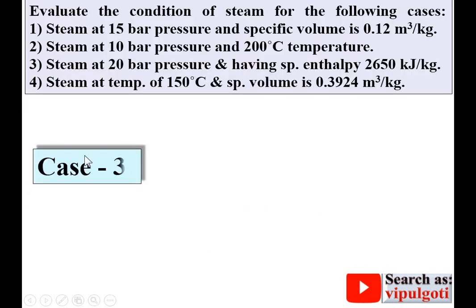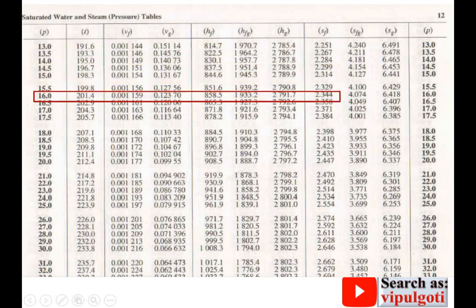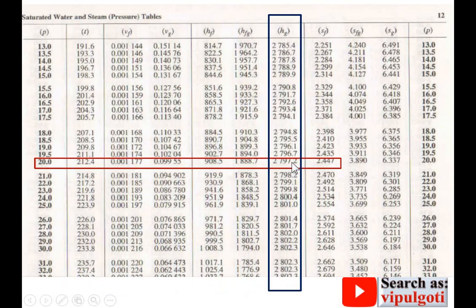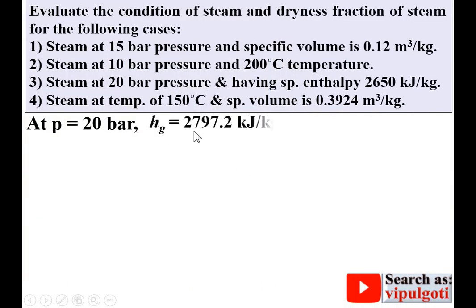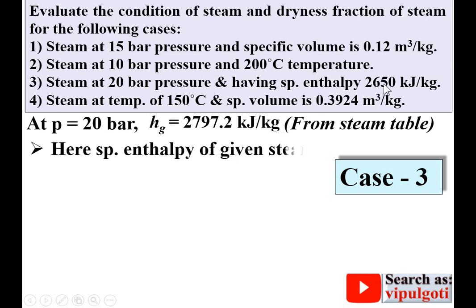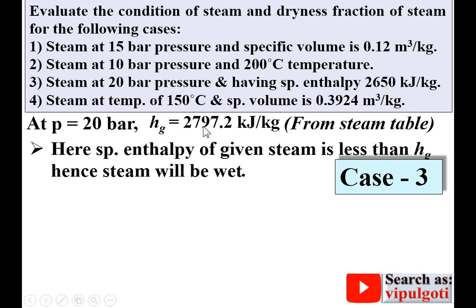Case three: steam at 20 bar pressure with specific enthalpy 2650 kJ/kg. From the steam table at 20 bar, Hg = 2797.2 kJ/kg. The given specific enthalpy of 2650 kJ/kg is less than 2797.2 kJ/kg, so the steam is wet steam.